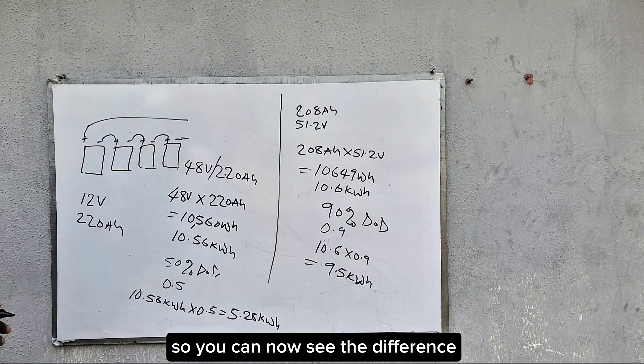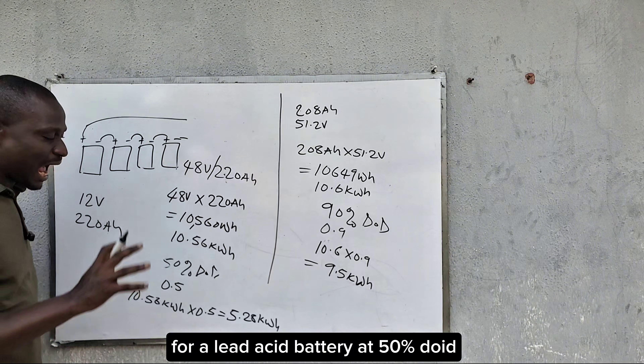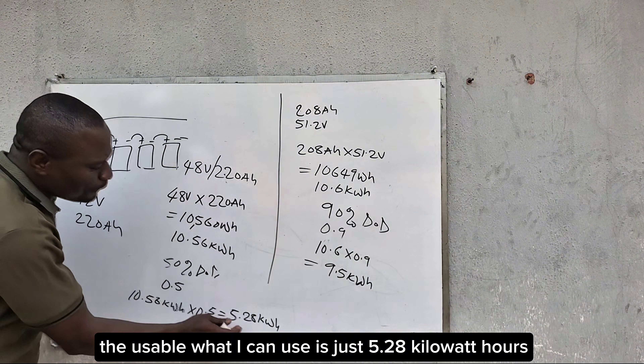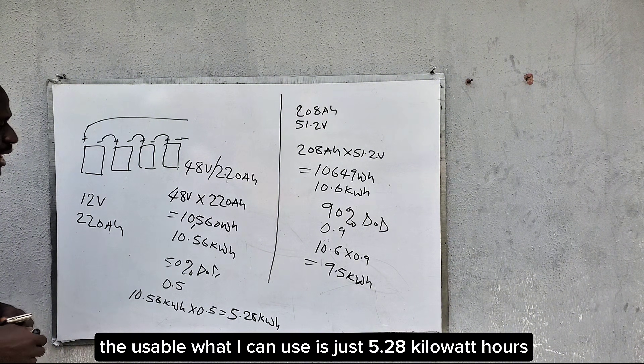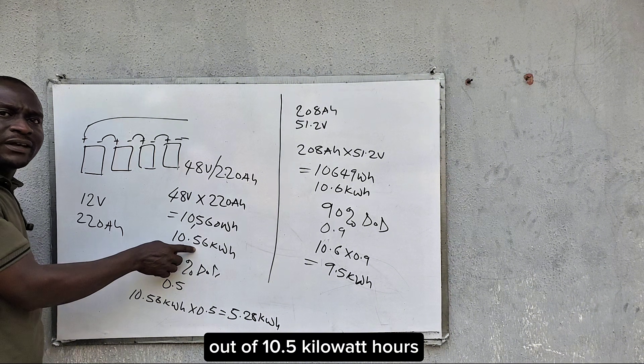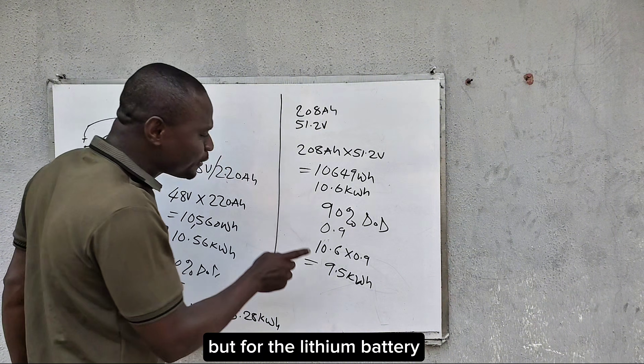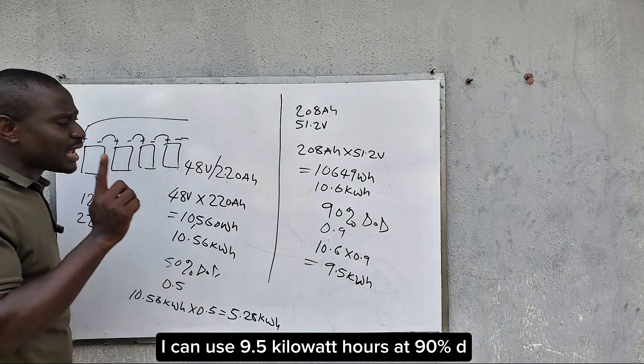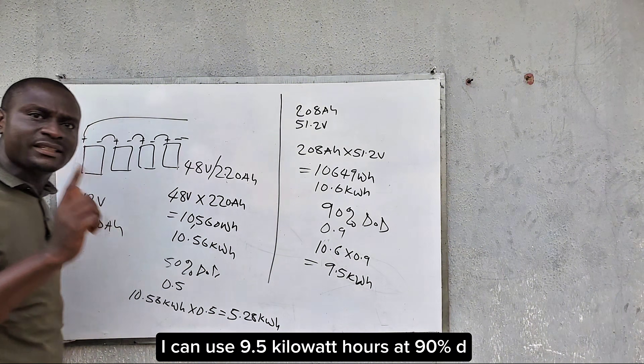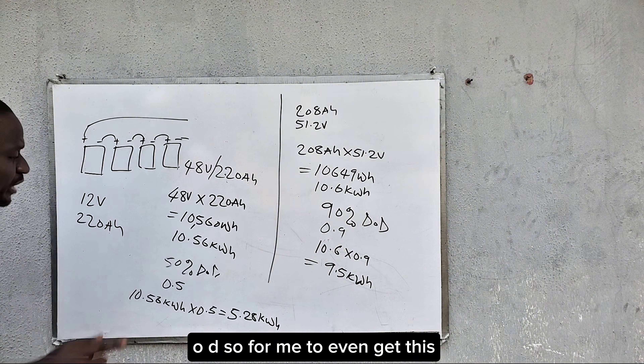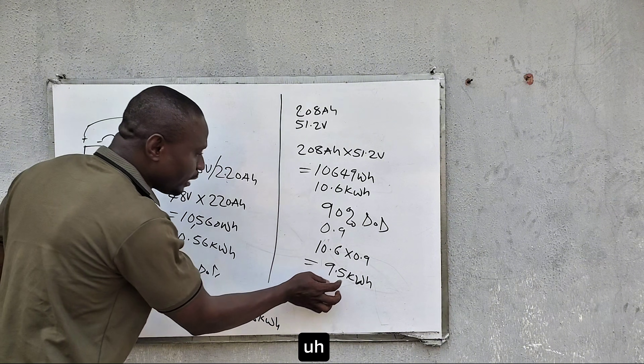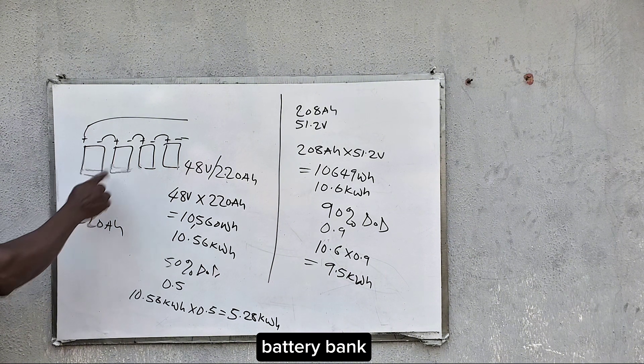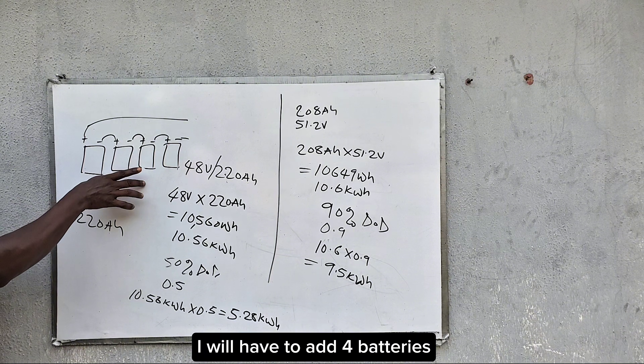You can now see the difference. For a lead acid battery at 50% DoD, the usable energy is just 5.28 kilowatt hours out of 10.56 kilowatt hours. But for the lithium battery I can use 9.5 kilowatt hours at 90% DoD. To even get close to that usable capacity with lead acid batteries, I would have to add four more batteries.